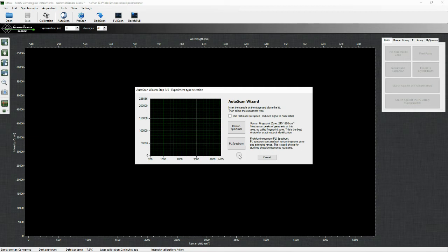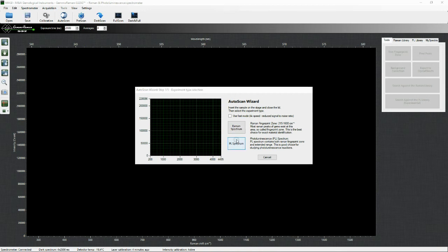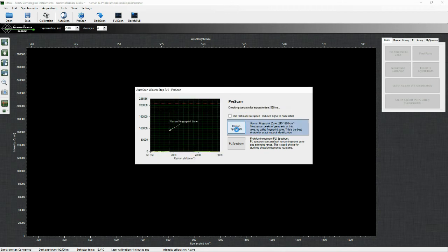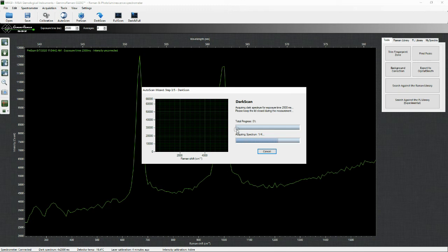There is no specific approach about which measurement type to select first for an unknown material. A good rule of thumb is to start with Raman mode measurements and switch to PL mode if the sample cannot be analyzed by the Raman spectrum. Click on Raman spectrum. The automated procedure will go through all the steps required for the identification of the unknown material. The last step will perform the search in the database and report the result. Those single steps will be described later one by one in the manual acquisition section video.